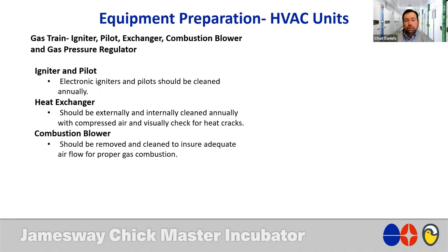The combustion blower should be removed and cleaned to ensure adequate airflow for proper gas combustion. Again, it's another little blower. It can collect dirt and debris. And if it's not in good physical condition, you won't have adequate airflow through the heat exchanger. And without the airflow, you won't have good gas combustion. And all of a sudden I lose heating capacity. So I may have a unit designed to operate at 300,000 BTU, and I may lose as much as 30 or 40% of my capacity if that combustion blower is just not moving adequate airflow.